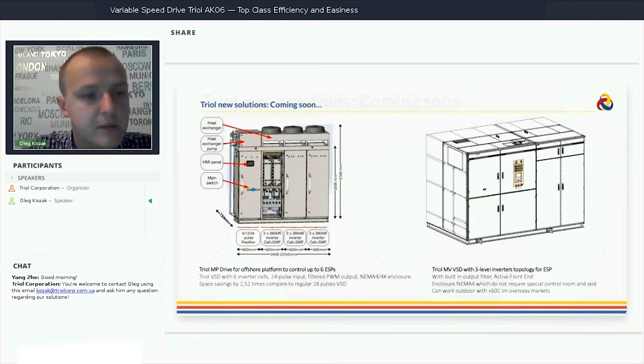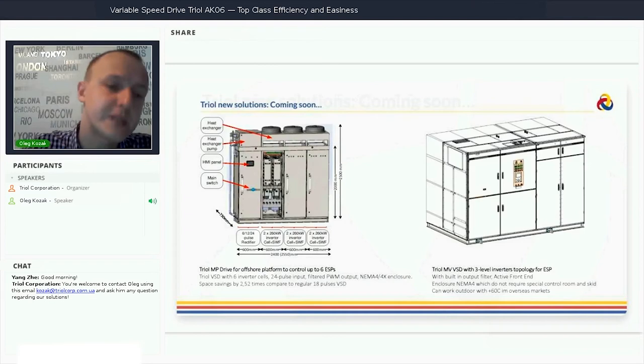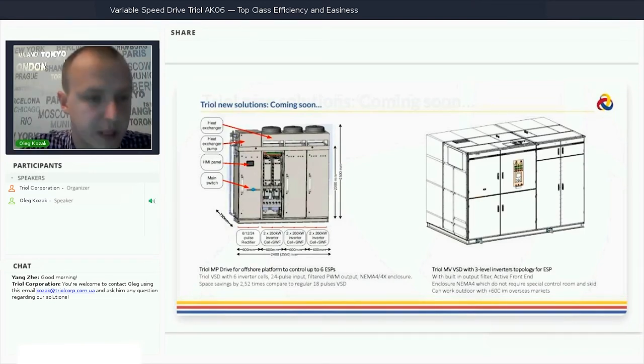So it's a space saving and cost effective solution for offshore platforms. The cooling system could be customized. As of today, it's a water cooling system with 24 pulse rectifier, so you don't need any input filter. It's a low voltage drive. You need only voltage supply 380, 480, and a step up transformer for several motors - 6 motors, 6 step up transformers. No input filter, sine filter built in.